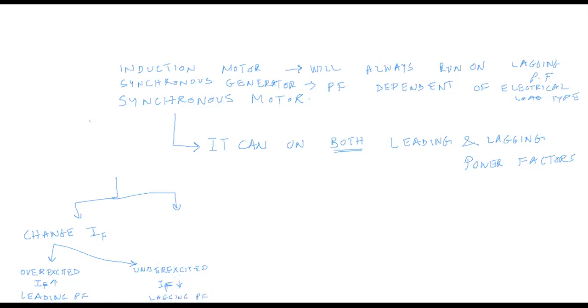Always remember these terms, overexcited and underexcited. If someone says the synchronous motor is overexcited, over means to increase something, and excitation is the field excitation. So if you increase the IF, the synchronous motor will begin to run at a leading power factor. That means the current drawn from the supply will lead the voltage of the supply.